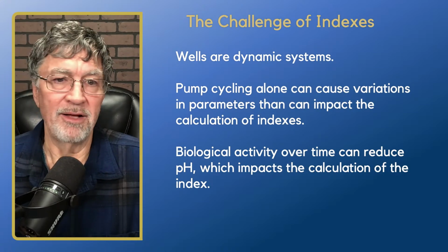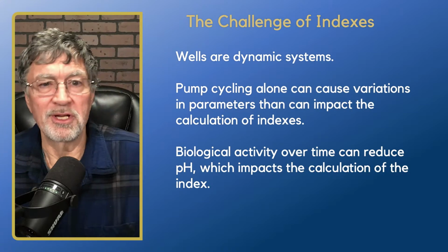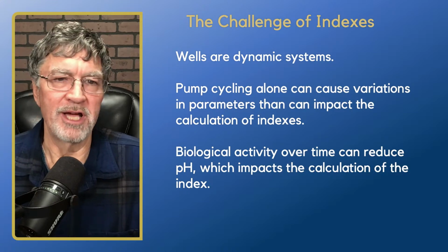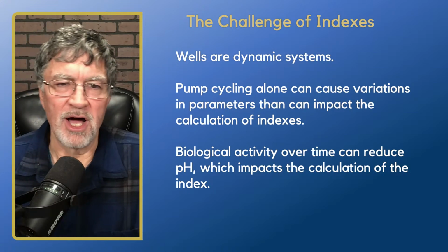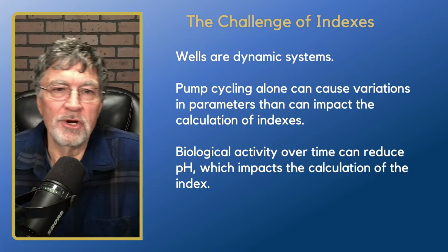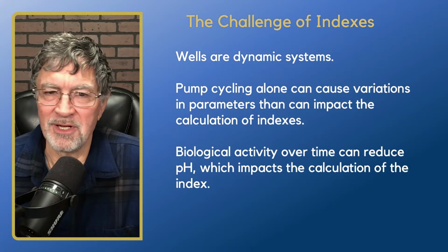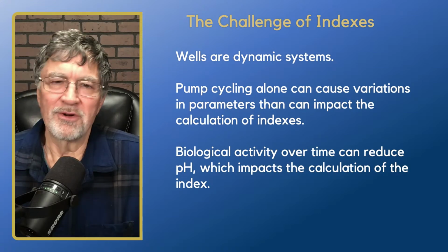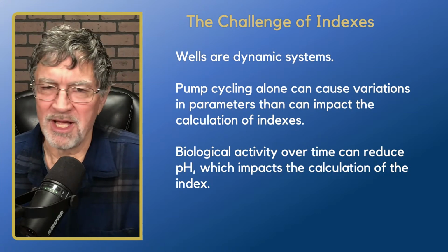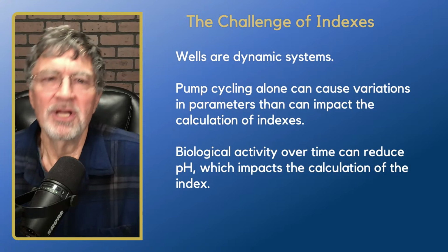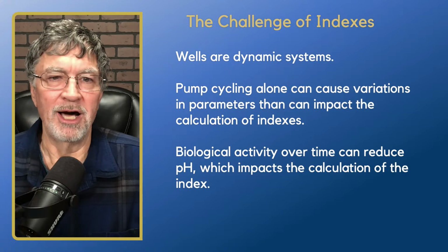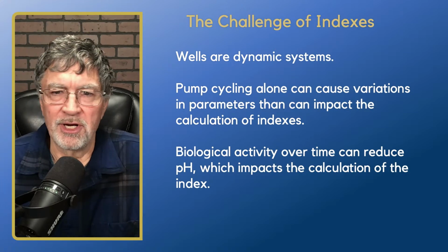With enough calcium carbonate there, you can start to get degassing of your calcium carbonate, which will release carbon dioxide, which will actually acidify the well, and now you're lowering the pH, which is going to push your LSI down into the negative range. So the more calcium carbonate scale you have in the well, the more potential you have for degassing and carbon dioxide formation, which will then lower your LSI and doesn't indicate what's going on at all. So that's a caution there.